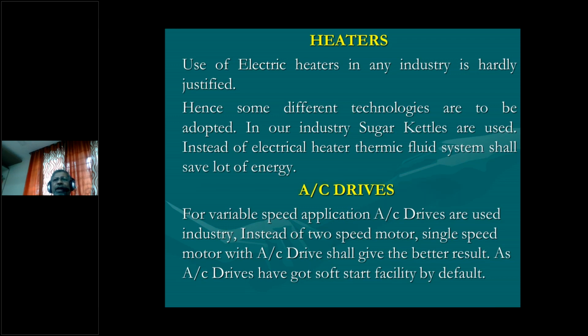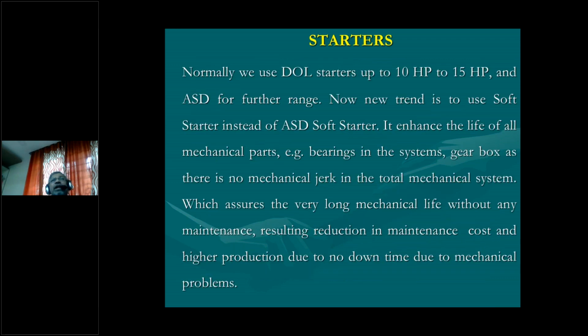A motor with AC drive shall give better results, as an AC drive has a soft start facility by default. Many times it is considered that an AC drive is only used for power saving. Power saving, yes, it is one of the aspects, but if you see the ID fans, FD fans, the diameter of the impellers is so high that the starting torque is tremendous. That motor takes more than 2 to 3 minutes to start, and your star delta starter doesn't work. They used to go for a DOL starter previously when there was not sufficient technology. Many times I have come across incidents due to heavy torque, the shearing of the shaft, where the motor used to run and the impeller got isolated, then the shearing of the shaft used to happen.